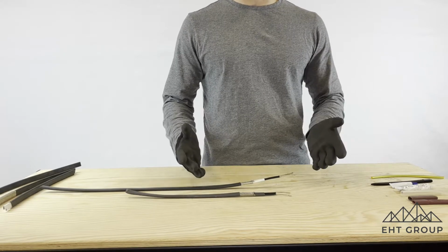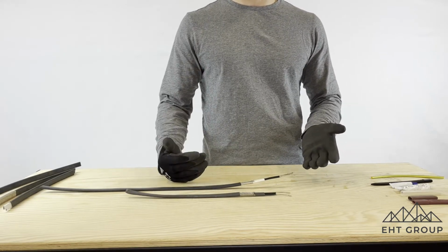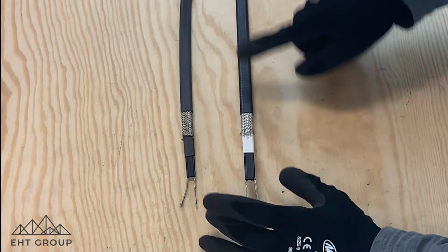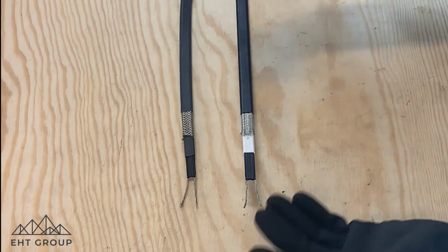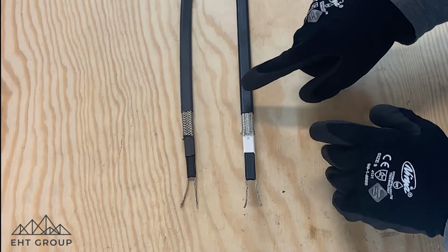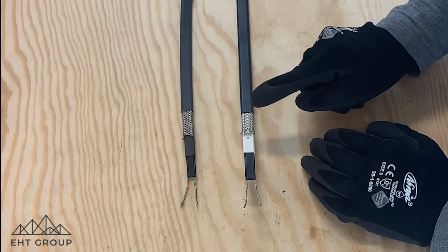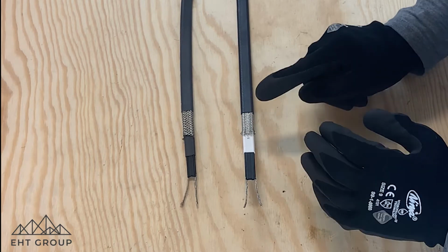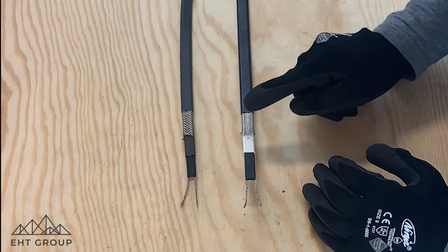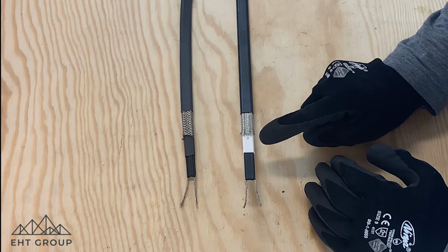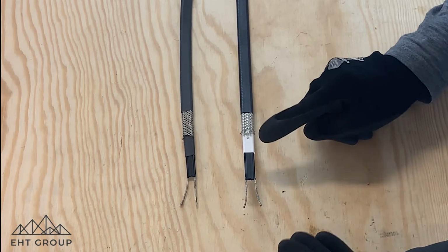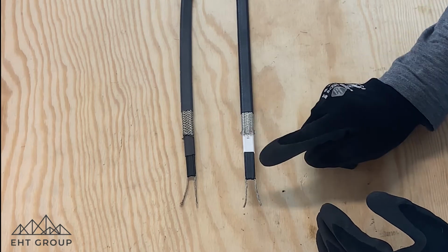So the basic components of an SR cable, and I have two different flavors of SR cable here, are the following. The first is we have an outer jacket. If this is going to be a harsh industrial environment that might see chemical exposure, the outer jacket will be made of a fluoropolymer jacket. The next component is the braid, and the braid is essentially the electrical ground of the SR cable. Next we have the inner insulation, which is also referred to as the electrical insulation. And then the next is our conductive polymer core wrap.